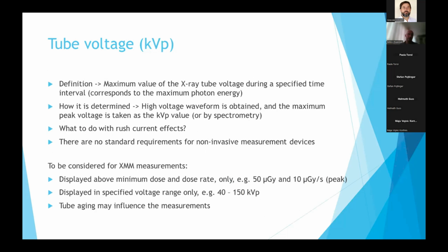So the next quantity that I will mention is maximum peak voltage. So the definition is relatively clear. You take the maximum value of voltage during a single exposure, and this is your maximum peak voltage, or kVp. So the definition in the standard is actually a maximum value during a specified time interval. So the only problem here is how you define the time interval.